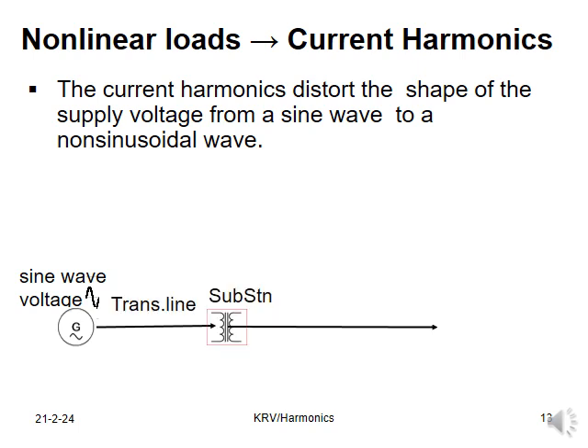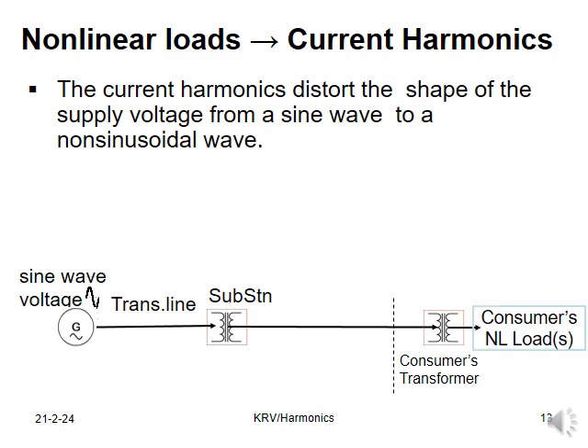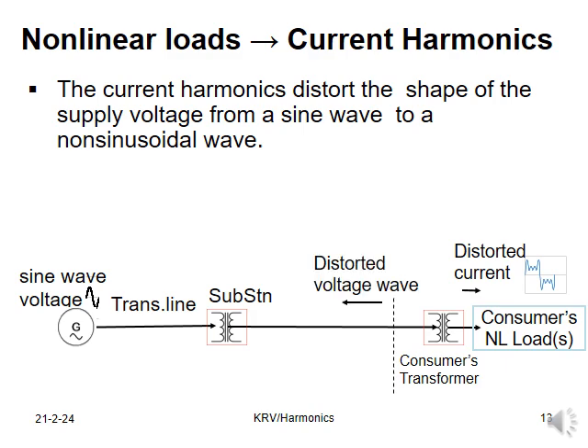From the substation, the power is transmitted to the consumer's transformer. The consumer's transformer supplies non-linear loads which take the load current in non-sinusoidal form. This distorted current distorts the voltage waveform, and this distorted voltage wave is applied to the other consumers.